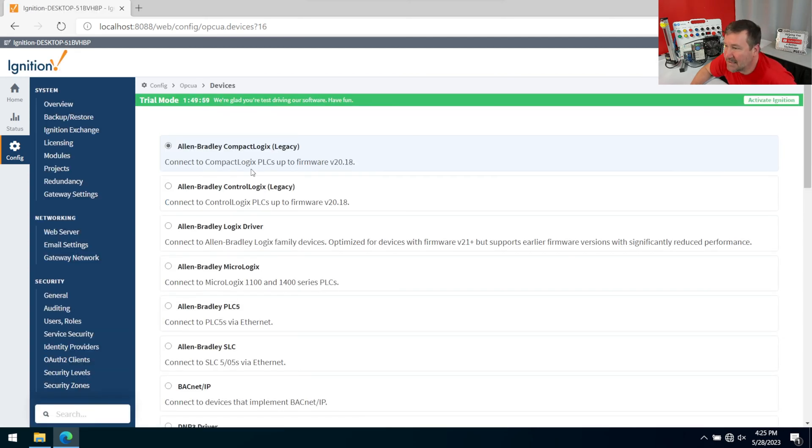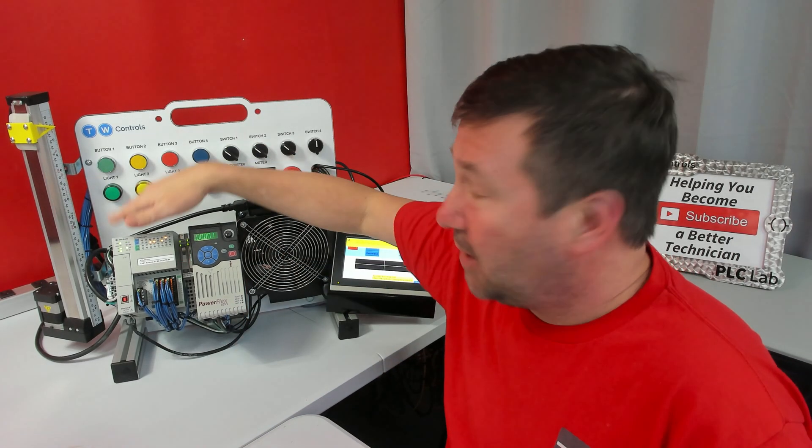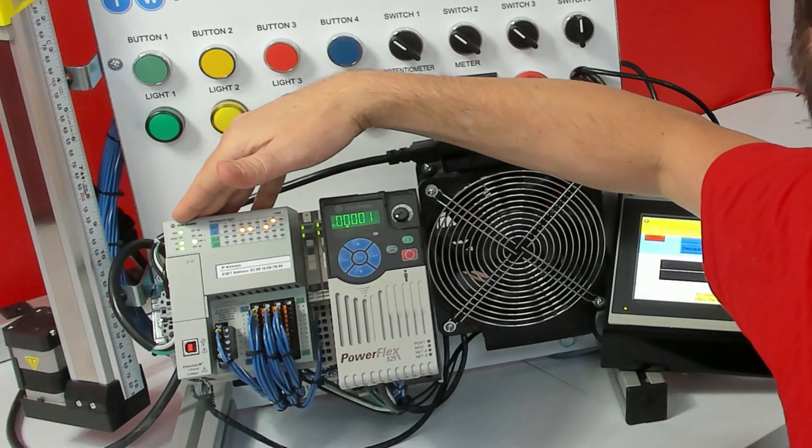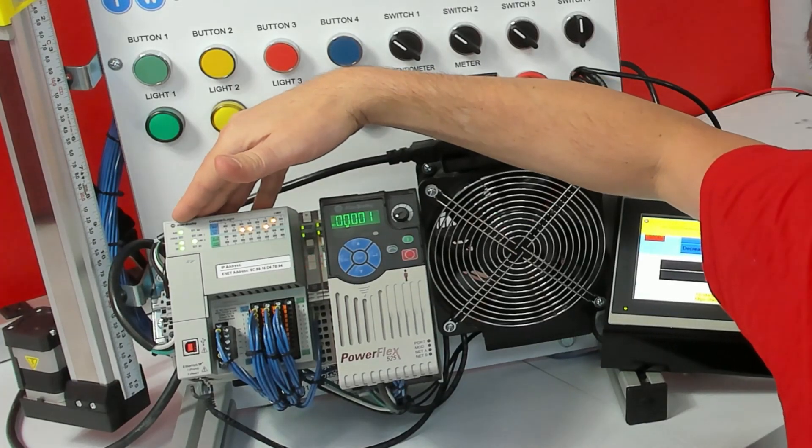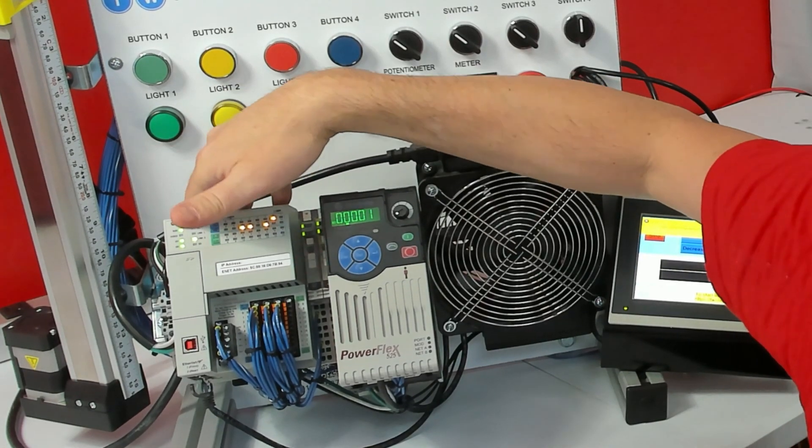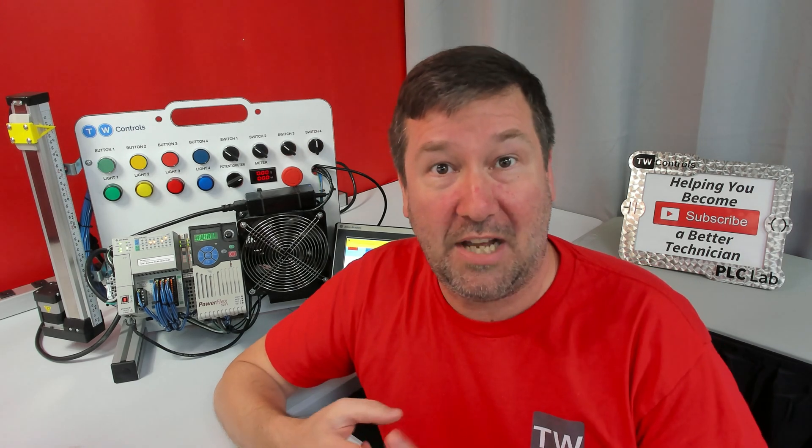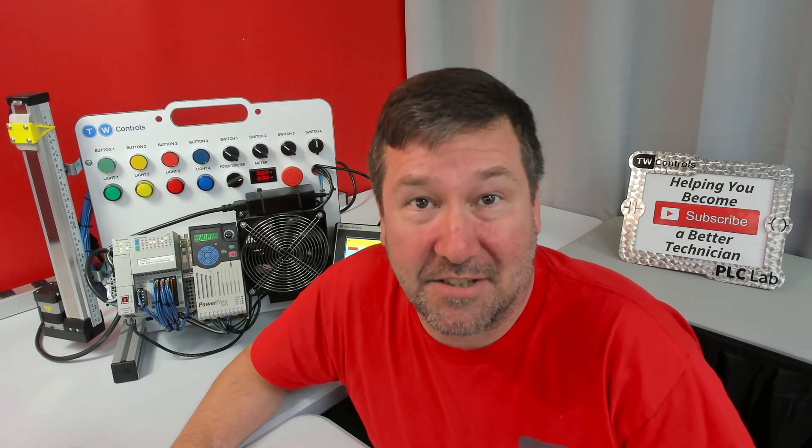This is going to be an Allen Bradley Logix driver, and it's going to be that because we are connecting to this compact logics, which is a 1769 L18. But any of your modern control logics and compact logics, that's the driver you'll use.